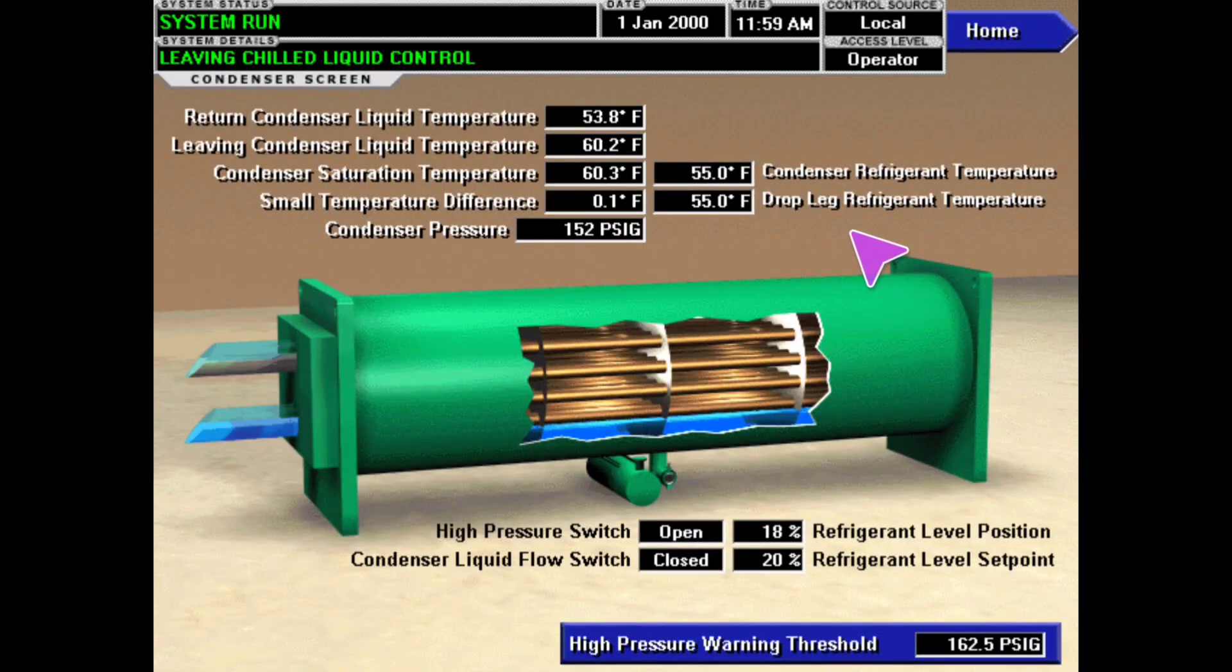Let's talk about chiller approach and how that impacts the system, how you calculate it, how you can use it, and just my overall thoughts and experience on it. Approach is the ability for your heat exchanger to exchange heat. It's a heat transfer rate where we're seeing how well the heat in the refrigerant on the outside of these tubes is able to transfer to the inside of the tubes and hit the water.